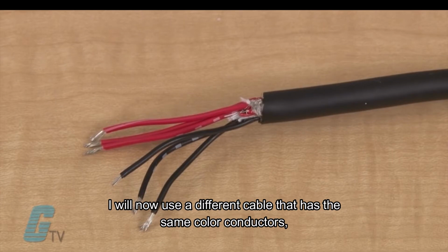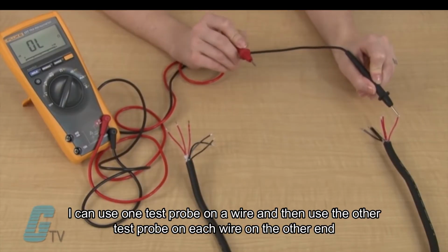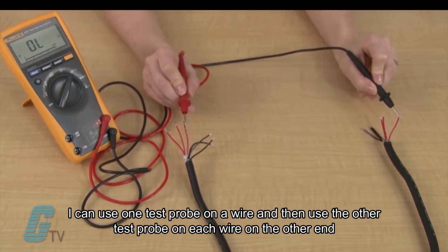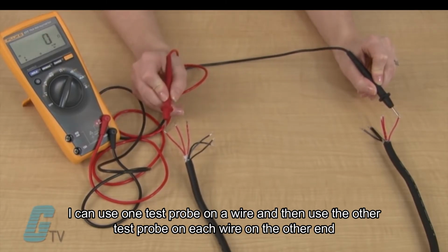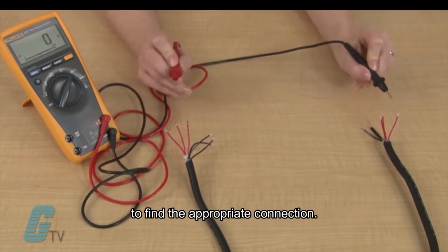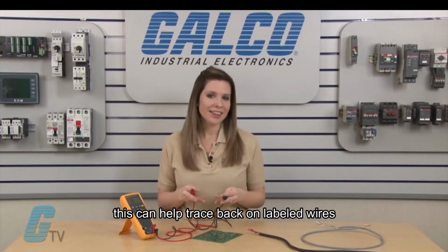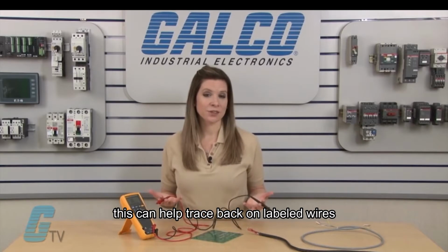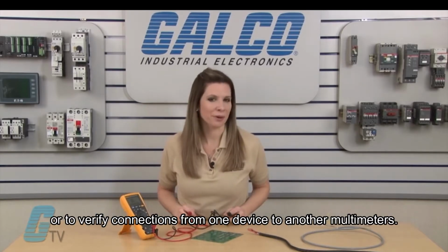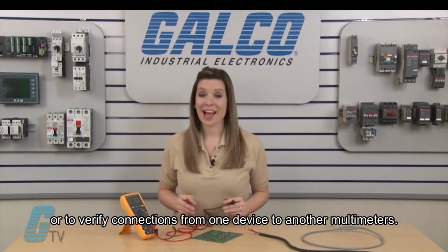I will now use a different cable that has the same color conductors. I can use one test probe on a wire and then use the other test probe on each wire on the other end to find the appropriate connection. This can help trace back on labeled wires or to verify connection from one device to another with multimeters.